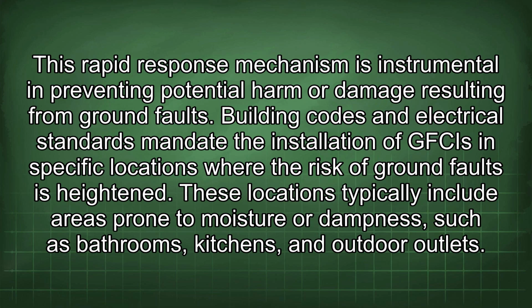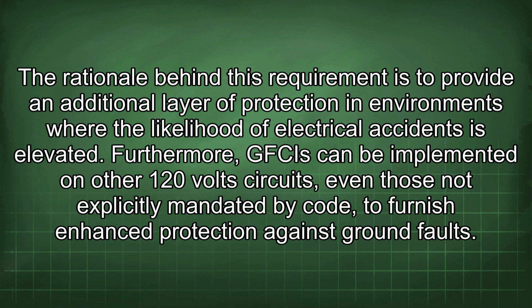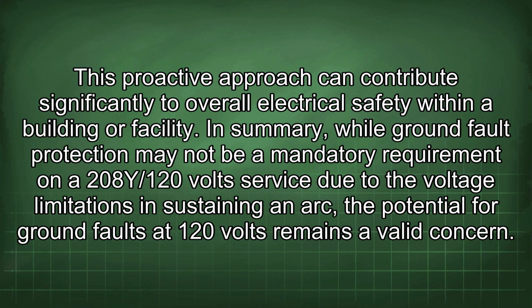Building codes and electrical standards mandate the installation of GFCIs in specific locations where the risk of ground faults is heightened. These locations typically include areas prone to moisture or dampness, such as bathrooms, kitchens, and outdoor outlets. The rationale behind this requirement is to provide an additional layer of protection in environments where the likelihood of electrical accidents is elevated. Furthermore, GFCIs can be implemented on other 120-volt circuits, even those not explicitly mandated by code, to furnish enhanced protection against ground faults. This proactive approach can contribute significantly to overall electrical safety within a building or facility.